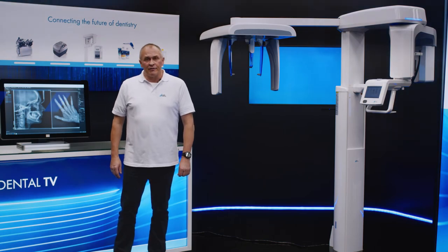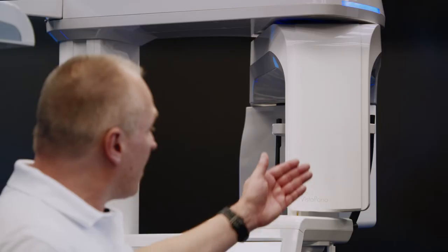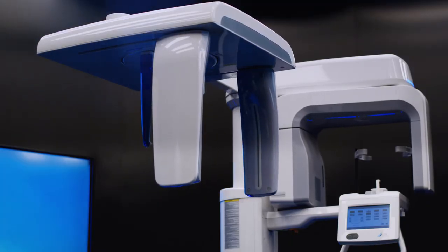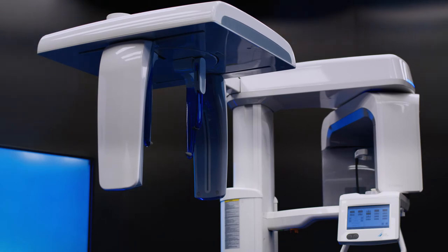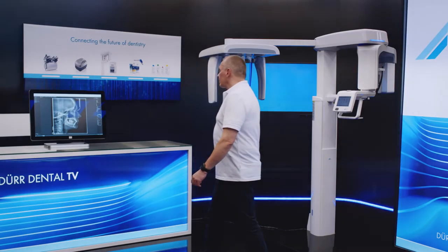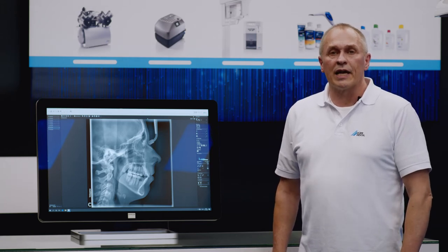A version of the Vista Pano SF with a module for cephalometric projections, which are very popular primarily in joint practices and orthodontic practices, is also available. The system comes complete with two CCD sensors, one for panoramic images and one for cephalometric exposures. As soon as the desired program has been selected, the system switches position automatically so that the operator can concentrate fully on the patient. The most frequent x-ray image taken with the ceph module is an image of the natural skull from the side, which takes just 4.1 seconds to create, virtually eliminating the risk of a patient moving whilst the x-ray image is being captured.